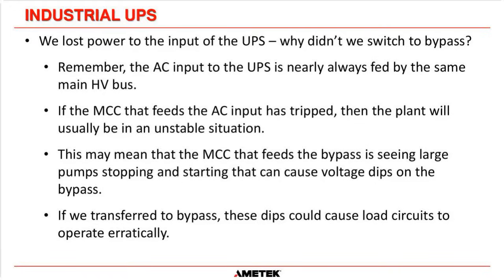If we stay on inverter and have the batteries provide power through the inverter, then it doesn't matter what the bypass is doing. The inverter is going to be perfect, 120 volts, 60 hertz going to your load circuits. It does not matter what the bypass or what's going on in the plant. It will be rock solid, 120 volts, 60 hertz, and your load circuits will be protected. That is why we do not switch to bypass, even though it is available if we lose AC power into the UPS.